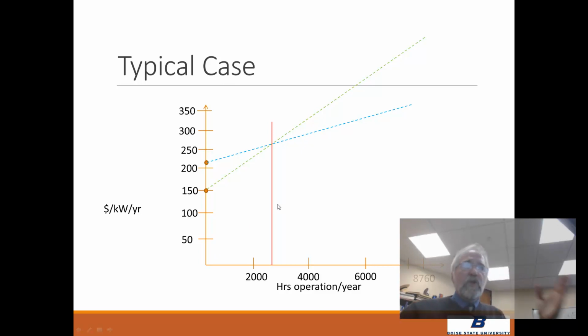And so there's this trade-off between maybe less expensive, high variable cost operation, and this is, for example, what a gas peaker plant is like. They're very cheap to build, but they cost a lot to run. Those are good if you only need them a few hundred hours in a year. In fact, that's what they build them for. They're called peaker plants. They're only used on those really peak days. But really expensive plants with more modest variable cost, like pulverized coal, those are good if you have them on all the time, right? You need to run them a lot of the time.